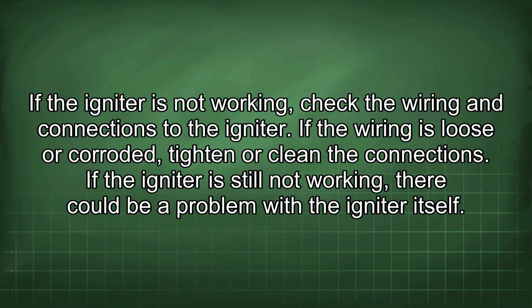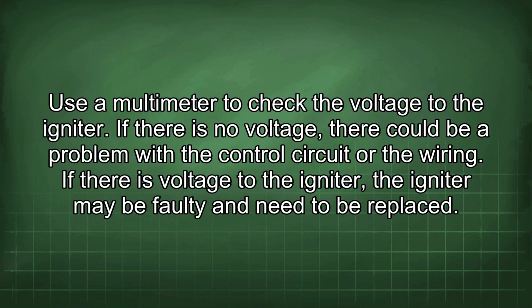If the igniter is not working, check the wiring and connections to the igniter. If the wiring is loose or corroded, tighten or clean the connections. If the igniter is still not working, there could be a problem with the igniter itself. Use a multimeter to check the voltage to the igniter. If there is no voltage, there could be a problem with the control circuit or the wiring. If there is voltage, the igniter may be faulty and need to be replaced.